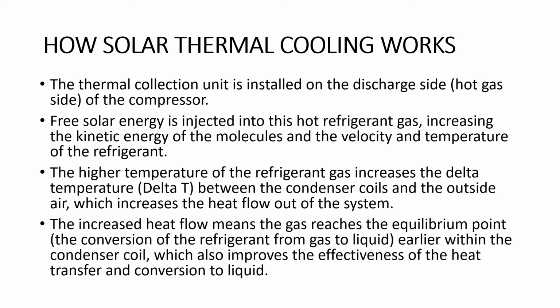So how does solar thermal cooling work? The thermal collection unit is installed on the discharge side, the hot gas side, of the compressor. Free solar energy is injected into this hot refrigerant gas, increasing the kinetic energy of the molecules and the velocity and the temperature of the refrigerant. The higher temperature of the refrigerant gas increases the delta temperature, we call it delta T, between the condenser coils and the outside air, which increases the heat flow out of the system. The increased heat flow means the gas reaches the equilibrium point, which is the conversion of the refrigerant from gas to liquid, earlier within the condenser coil, which also improves the effectiveness of the heat transfer and conversion to liquid.